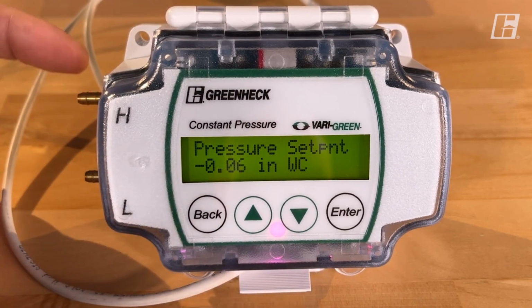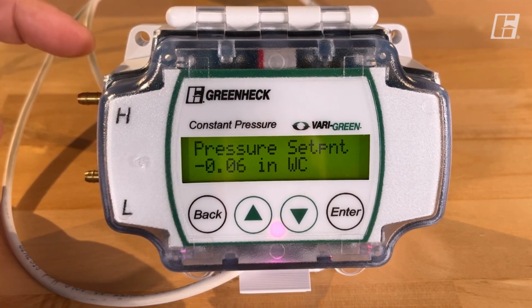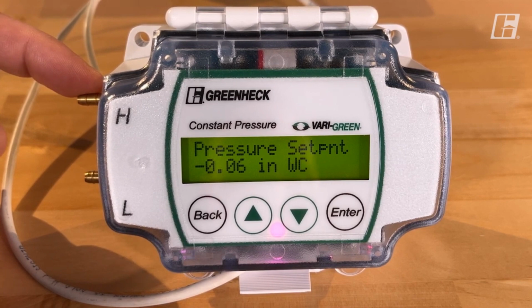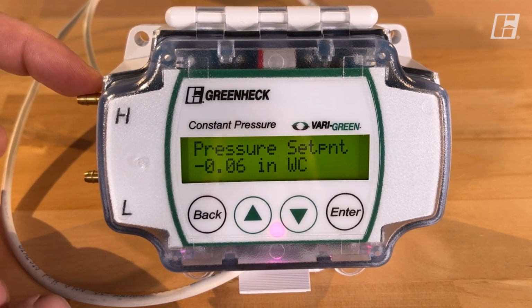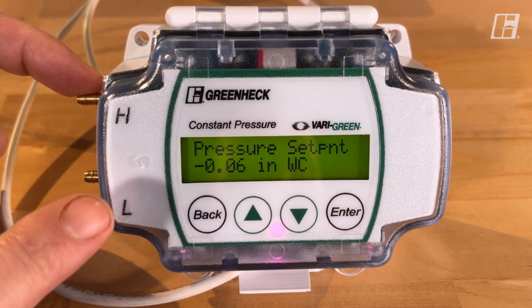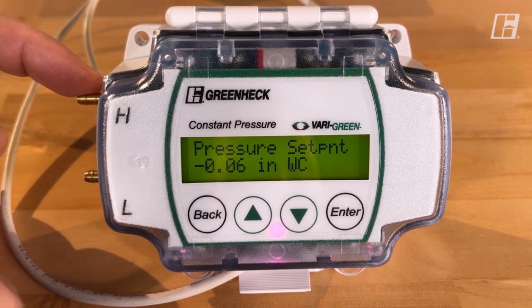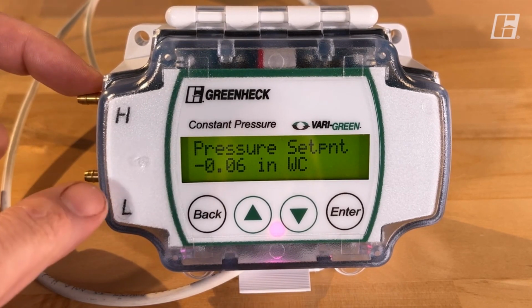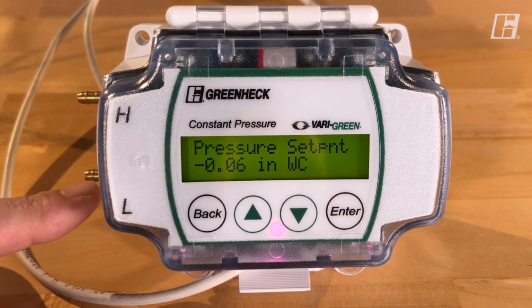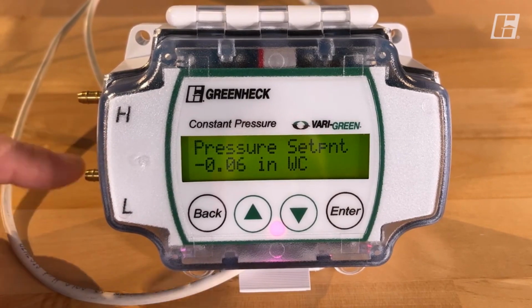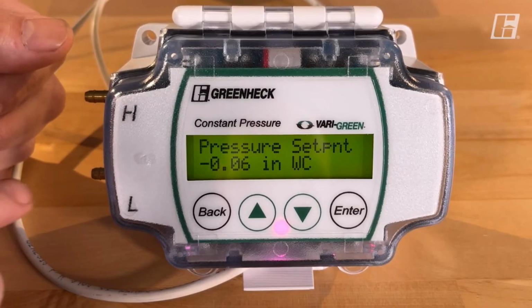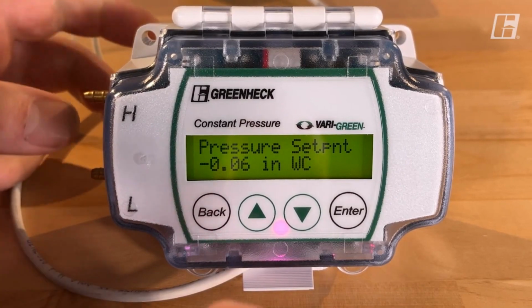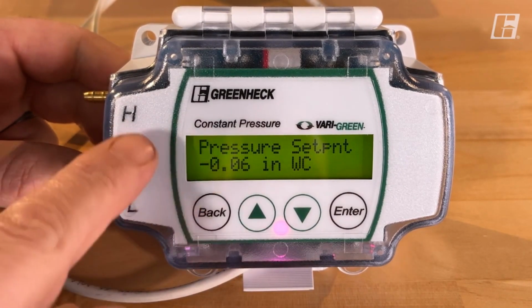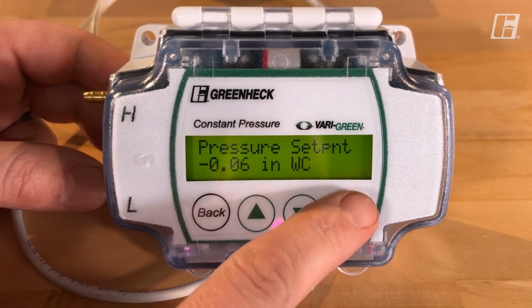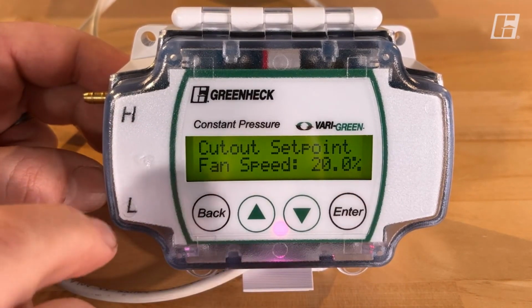All right, so in our little scenario, let's say we have a bath fan and I'm monitoring the pressure using the high port in the ductwork. And when the bath fan goes on, pressure in the ductwork goes up. This is going to then speed the fan up and pull that air out of the ductwork. For this scenario, my low port is just going to be left open because we're using the building space for ambient pressure reading. All right, so negative 0.06, that's what we want to maintain. I'm going to hit enter.